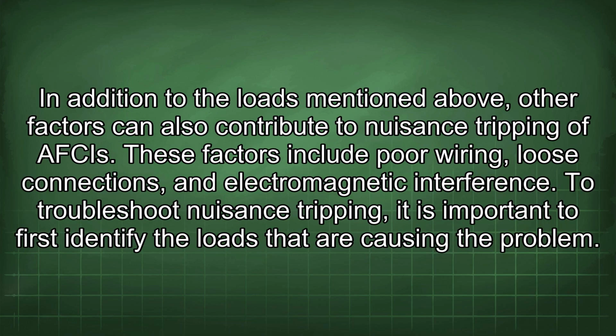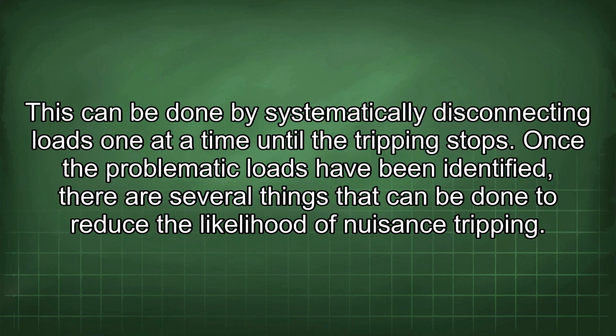In addition to the loads mentioned above, other factors can also contribute to nuisance tripping of AFCIs. These factors include poor wiring, loose connections, and electromagnetic interference. To troubleshoot nuisance tripping, it is important to first identify the loads that are causing the problem. This can be done by systematically disconnecting loads one at a time until the tripping stops.